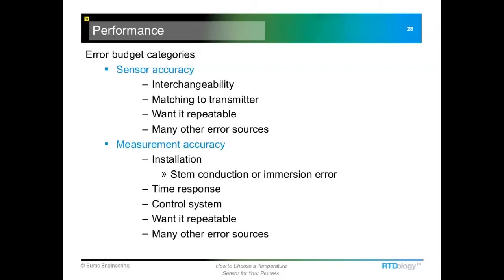The next section here is going to be on just looking at the performance of the sensor as it's installed in the process. So we've got two different categories here, the sensor accuracy and the actual measurement accuracy. And they can be quite different based on how the sensor is installed in the process.